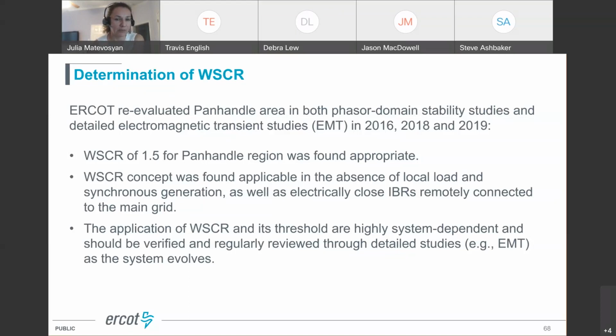We found this concept applicable in the absence of local load and synchronous generation in the area, as well as considering electrically close inverter-based resources that are remotely connected to the main grid. We want to point out that weighted short circuit ratio is highly system dependent, even the applicability of this metric, and it should be verified regularly through detailed studies such as EMT studies as the system evolves. So one of the examples I wanted to mention is that relatively recently Lubbock Power and Light system interconnected into the ERCOT area.